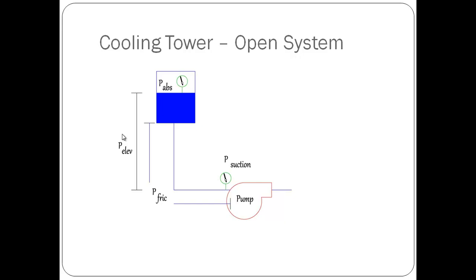Net positive suction head available is found by determining all the pressures acting upon the fluid, whether positive or negative. This figure describes all the pressures that may be acting on the pump for an open system like a cooling tower system.